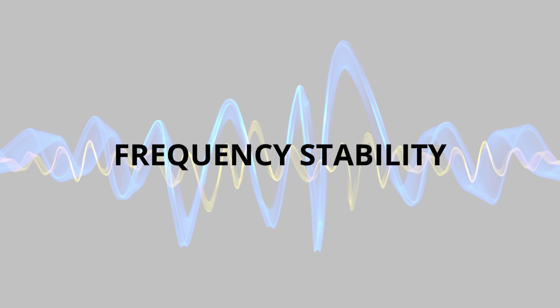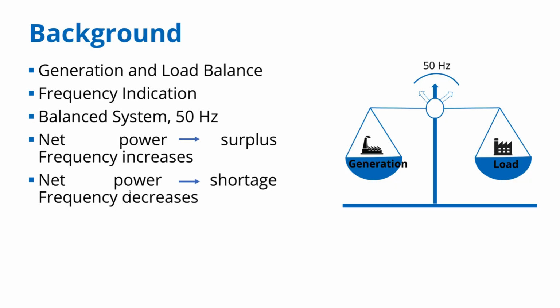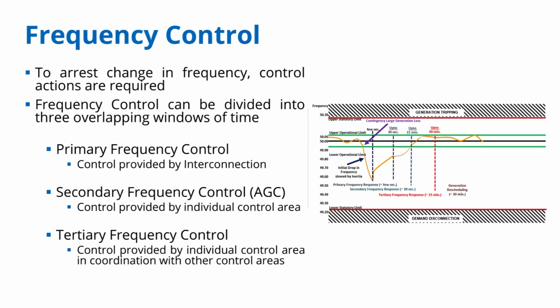Okay, final category presented. Frequency stability, back to generation and load balance. Yep, back to the basics. Frequency, the system's pulse rate, directly shows the real-time balance between total generation and total consumption plus losses. Balanced system, stable frequency. Imbalance, frequency deviates. Too much generation, frequency rises. Too much load, frequency falls. Because the system's rotational energy changes. Right, that's stored kinetic energy in all the spinning machines. The inertia acts as a buffer, but it can only absorb or supply energy temporarily. Frequency changes reflect changes in that stored energy.